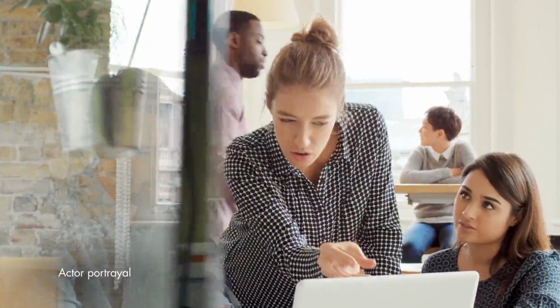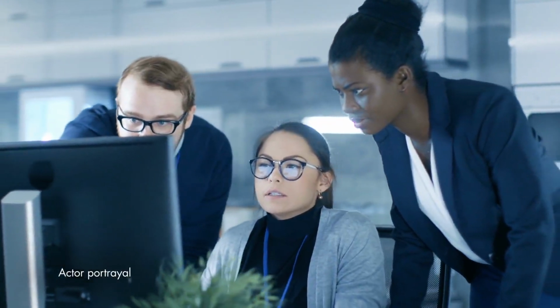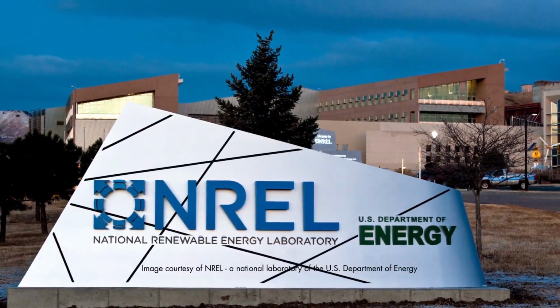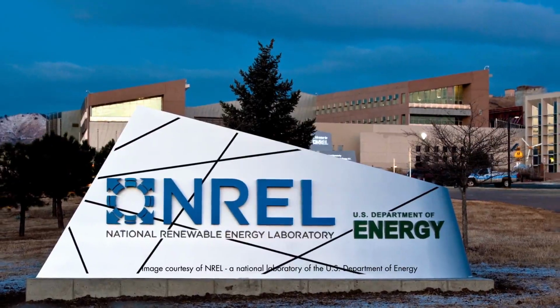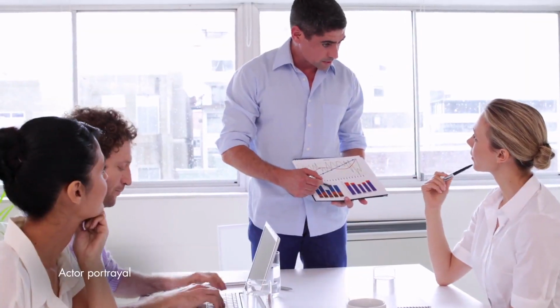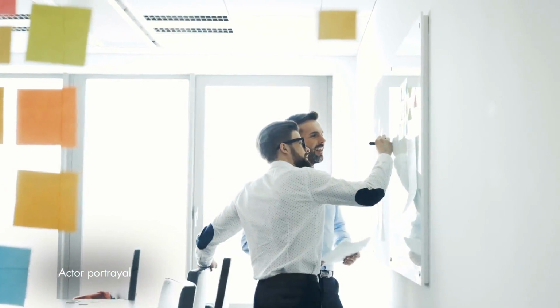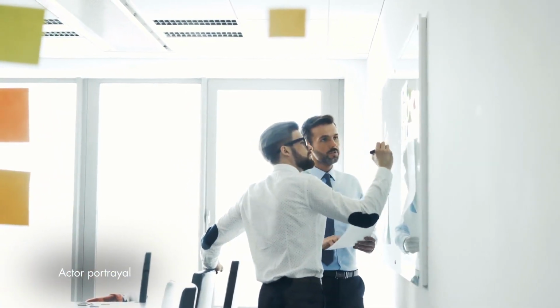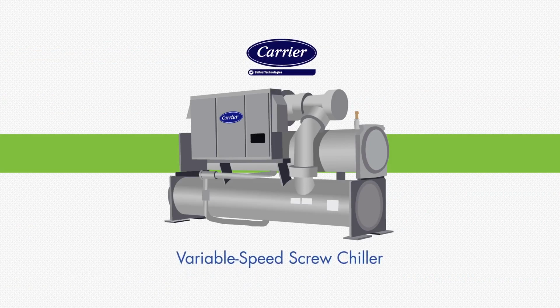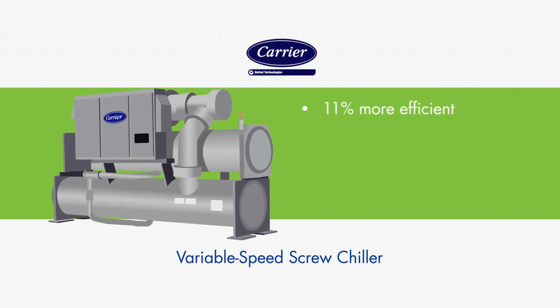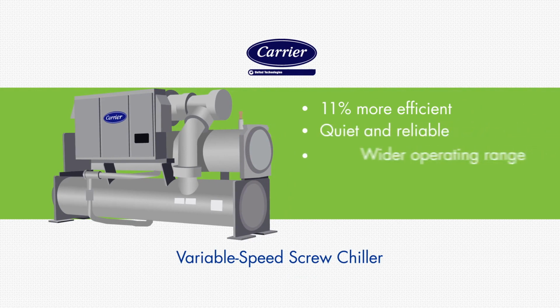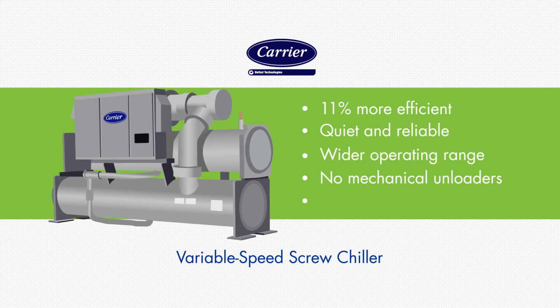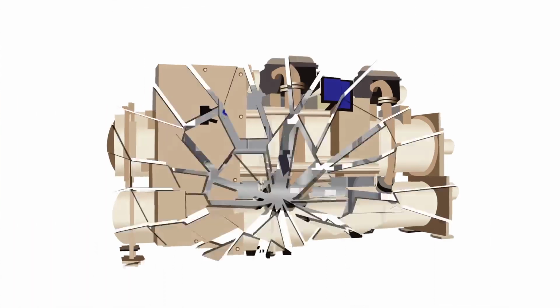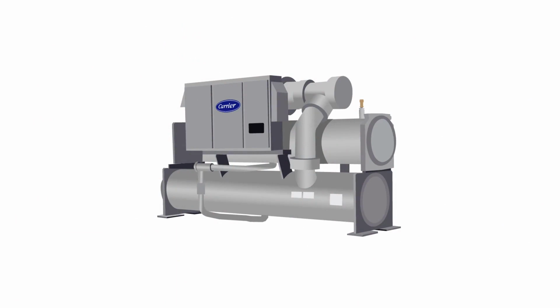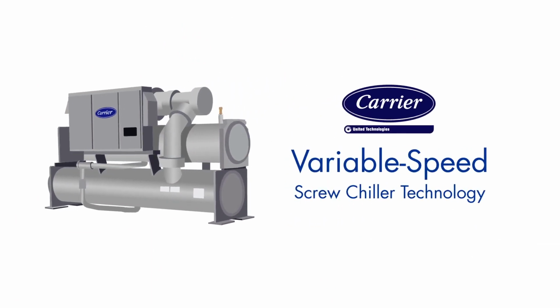At the request of other suppliers, the research team performed additional due diligence, including National Renewable Energy Lab's third-party review of test methodologies and data analysis, all of which affirm the conclusion originally reported in GSA Proving Ground Report number 31. In summary, the GSA Proving Ground findings on water-cooled chillers highlight the benefits of Carrier variable speed screw chiller technology: 11% greater efficiency, quiet and reliable operation over a wider range, and no mechanical unloaders, all with a lower cost. These findings shatter the common misconception that magnetic bearing chillers are the industry standard for efficiency and prove Carrier variable speed screw chiller technology sets a new level of performance.